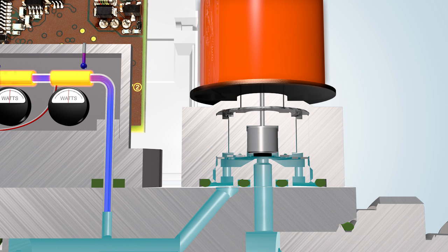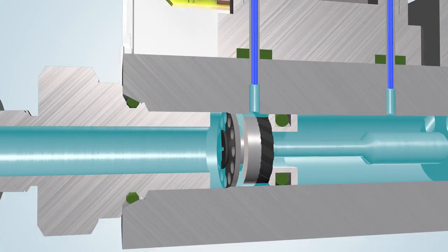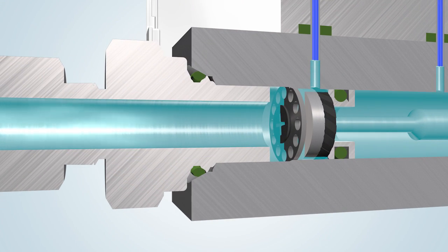The electromagnetic coil exerts a force on the magnetic plunger holder. This force is in balance with the linear springs that normally keep the control valve closed. As the plunger comes free from the orifice, the result is a flow through the instrument.